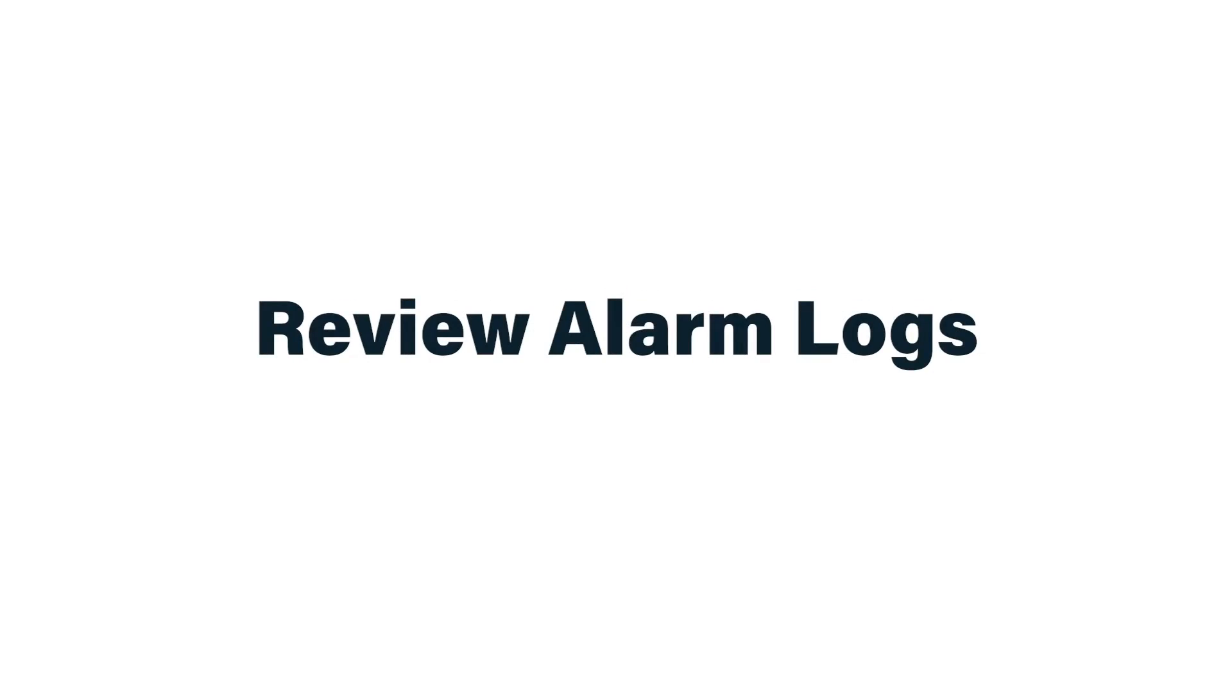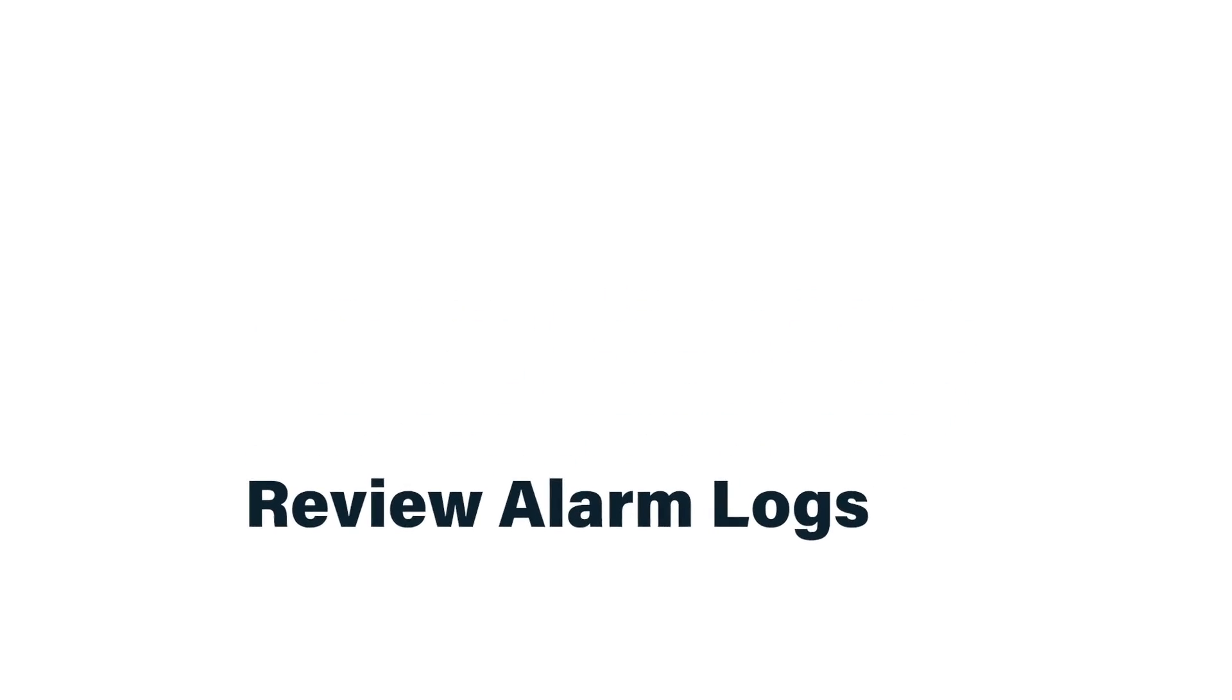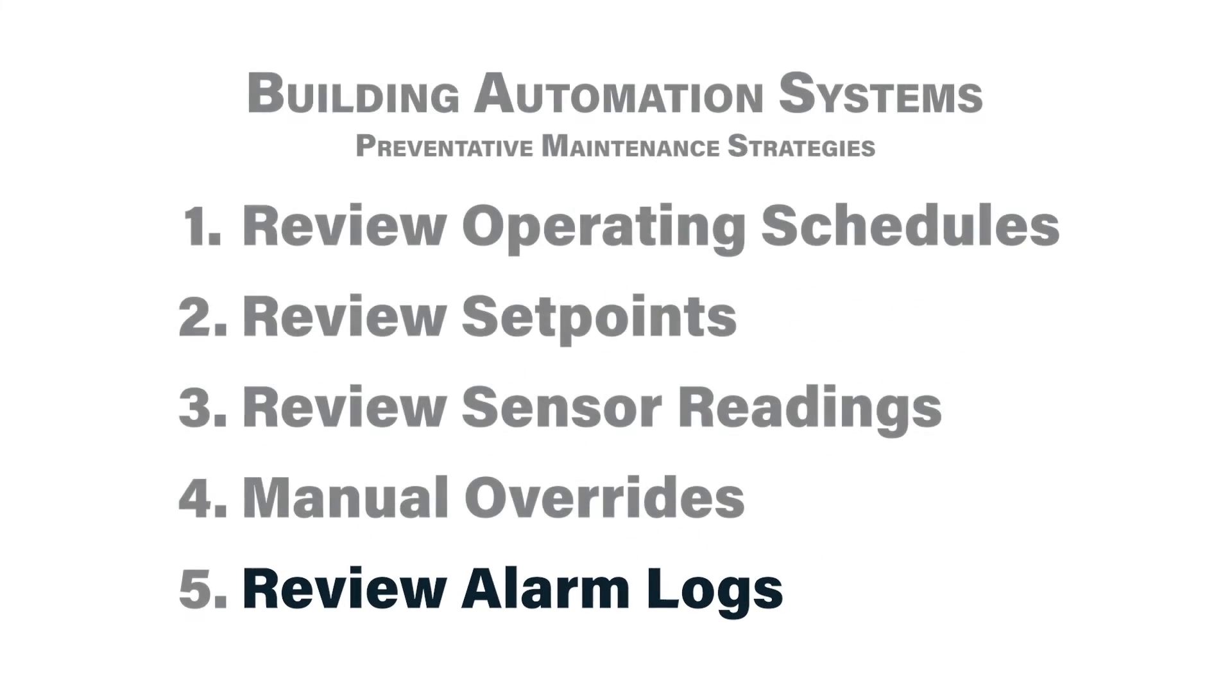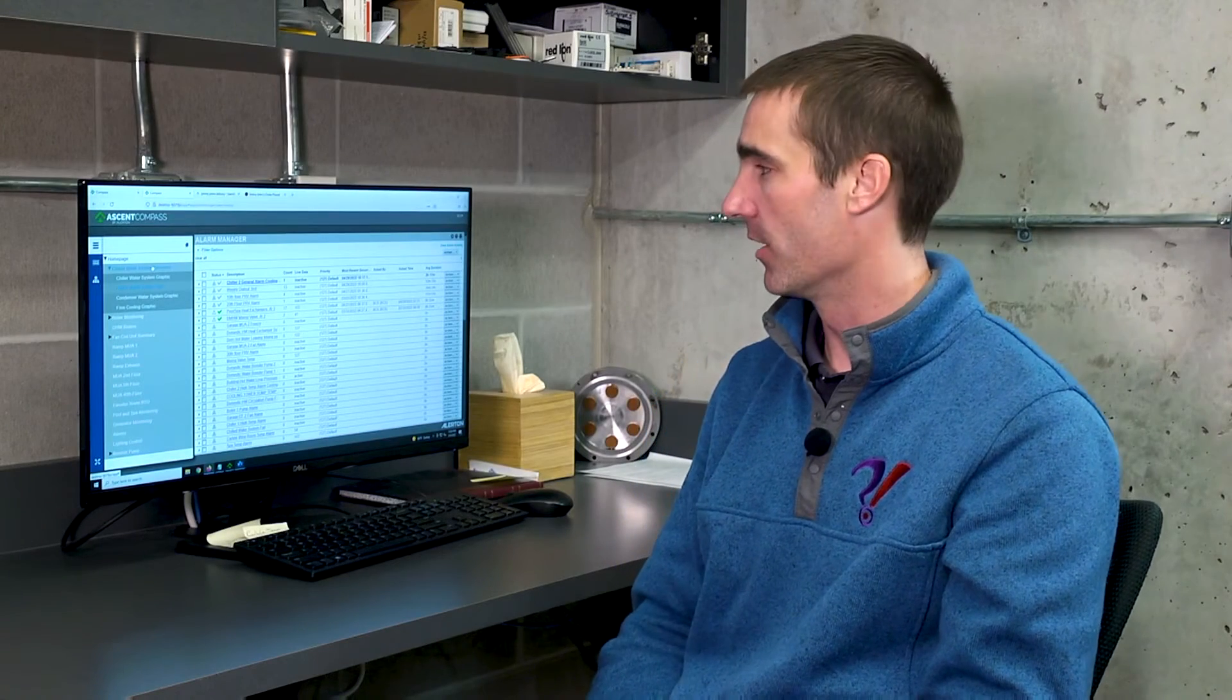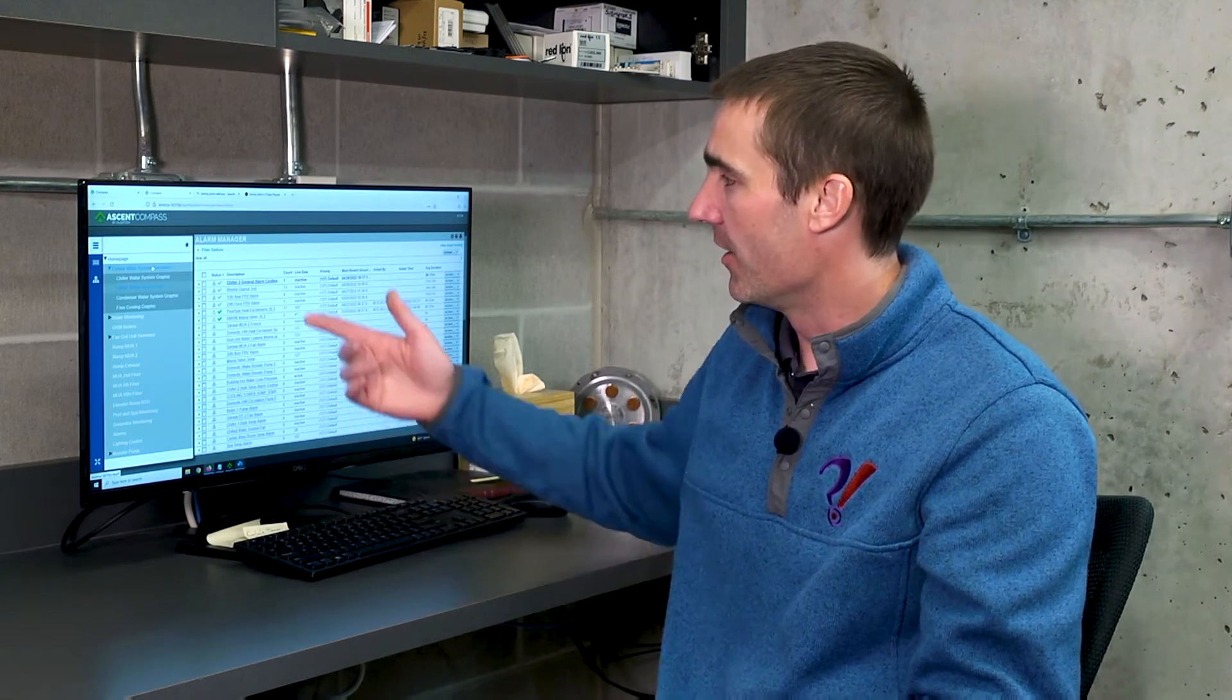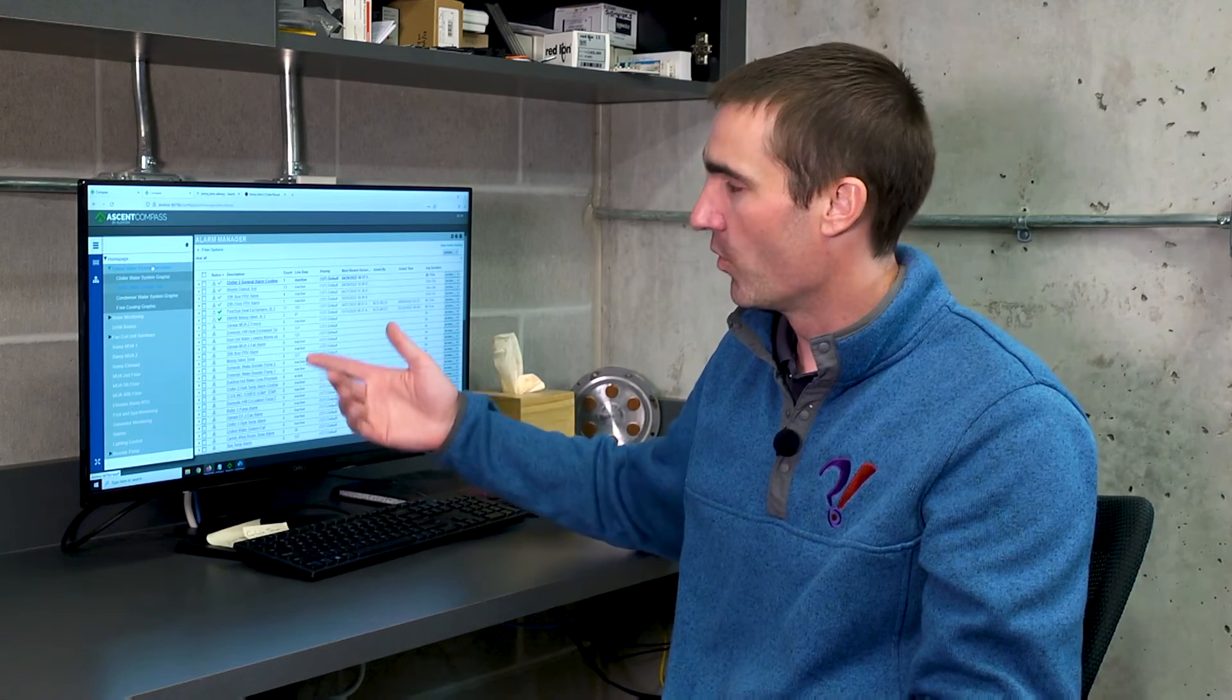The fifth preventative maintenance task you need to be performing on your building automation systems is a daily review of the alarm log. The alarm log is generated on the building automation system's user interface, and daily you should be logging into that, looking at what alarms have been generated, and when they were generated.